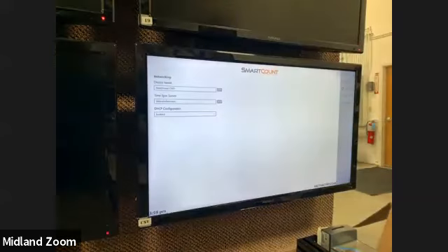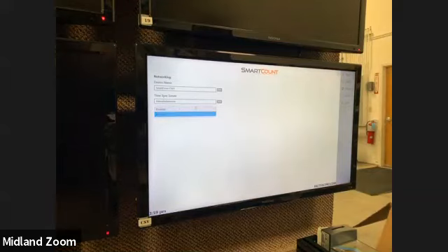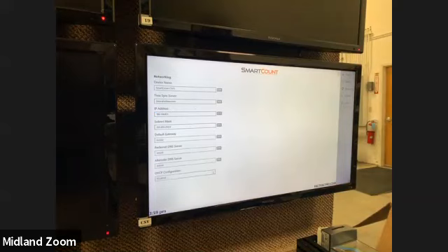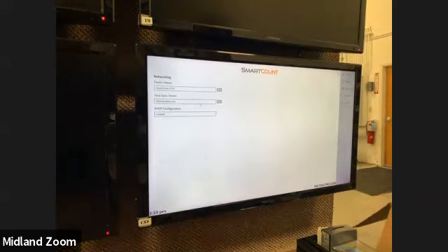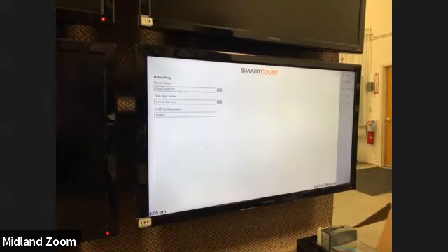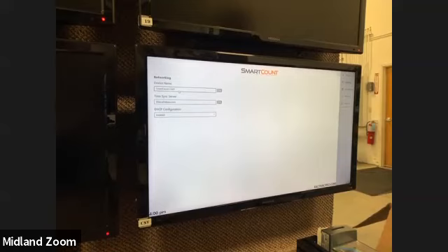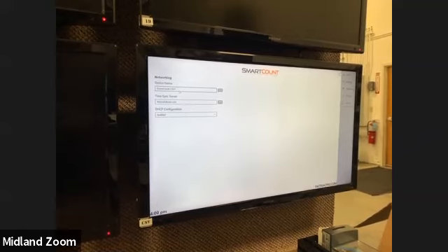So your networking page is going to be similar. If they want to disable the DHCP and enter all their own information, they can do that. For our area here, we just have the DHCP enabled. And again, you can name your device. So now this is a Smart Count CSV1. Each CSV unit will take up to 16 Smart Count Edge data streams. So if you had 20 smart counts, you would need two CSV units to handle that.